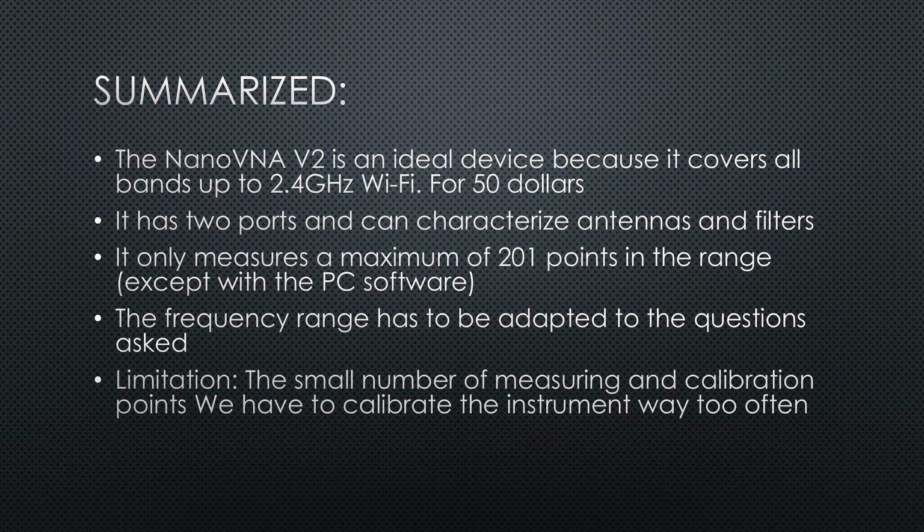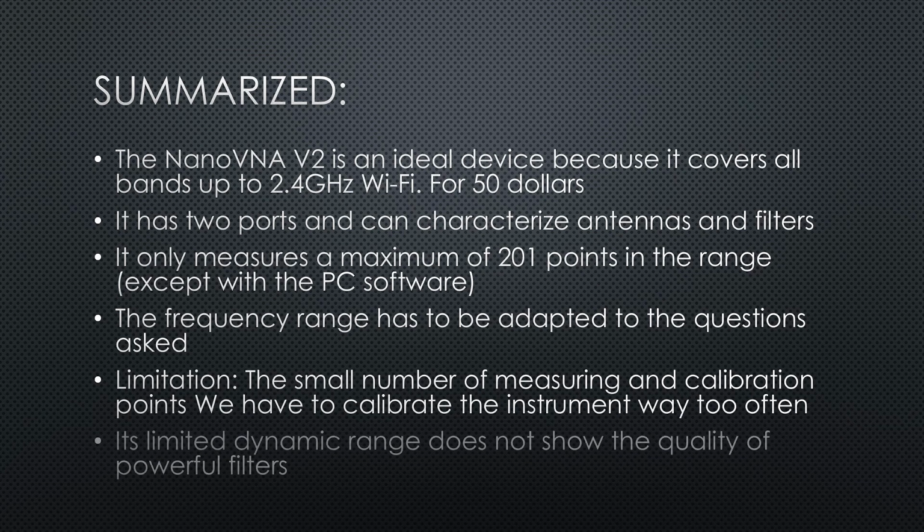The most important limitation is the small number of measuring and calibration points, with the effect that we have to calibrate the instrument way too often. Its limited dynamic range does not show the quality of powerful filters.